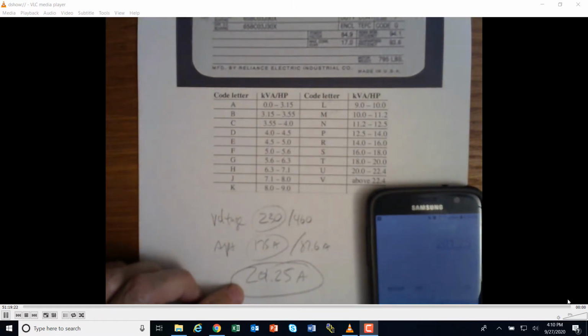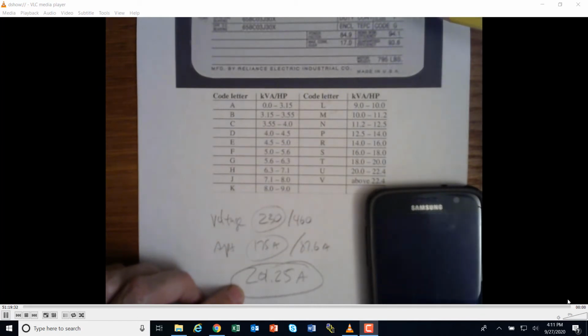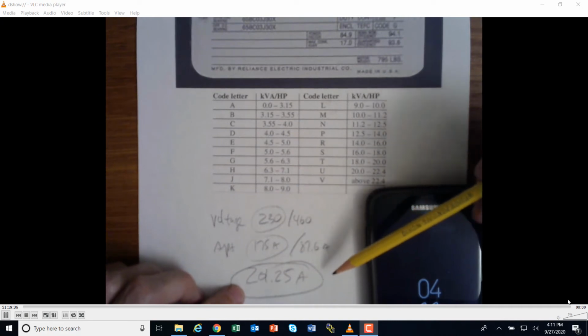Here, it's certainly going to run hot, based on it'll run in a 40 C ambient. And I don't see my insulation class on here, but that would tell us how hot this thing's going to run. So like I said, it's a pretty big, hefty duty motor. The other thing I'm seeing is that the enclosure is a totally enclosed fan cooled motor, so there are no vents or anything on this. This just has a fan that's cooling it.